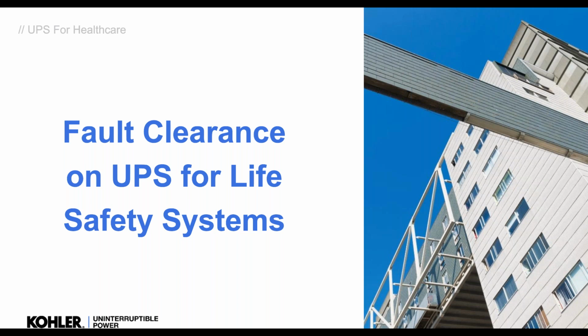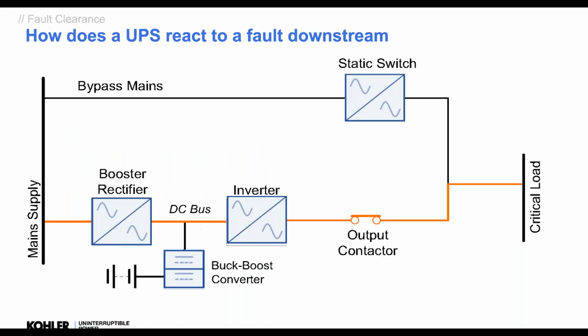Lot to get through. So we are now looking at fault clearance on UPSs, for health systems, for life safety systems. It's all the same. We are having critical supplies here. So how does the UPS actually react to this? Now, we have the main supply, and typically in an online static UPS, the load is running through the rectifier, producing a voltage which we connect to a battery, and then we convert the DC back to AC and feed the load in that manner. Okay, when we're on battery, we feed through this way.